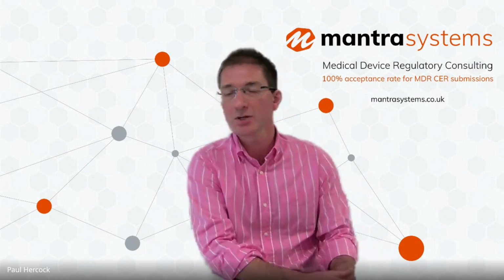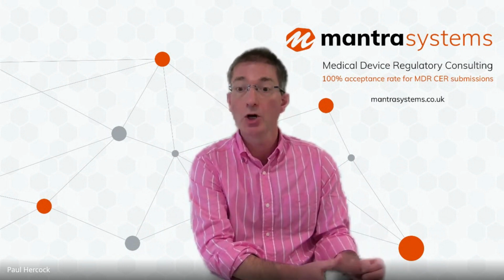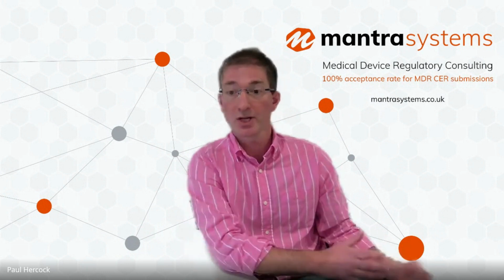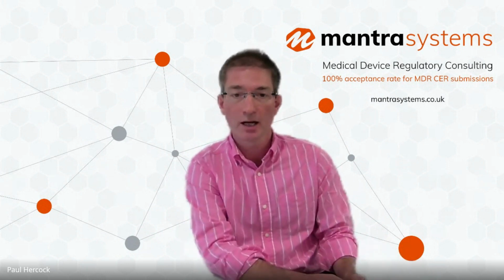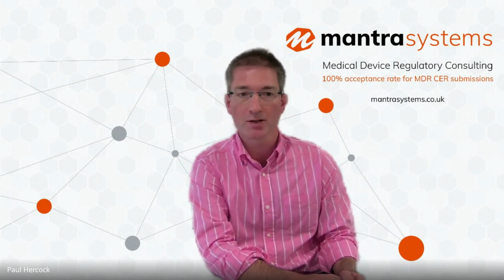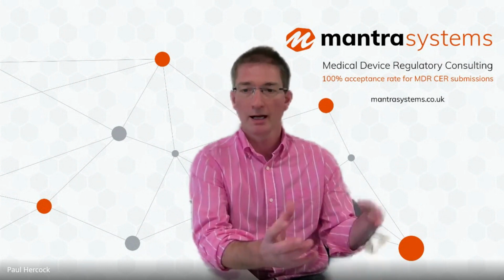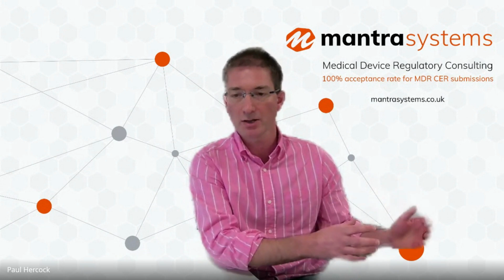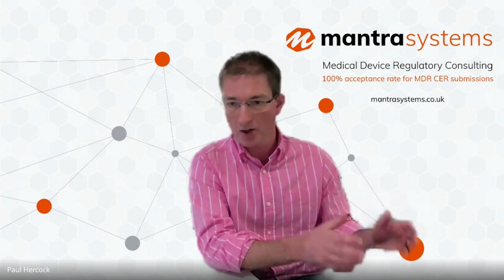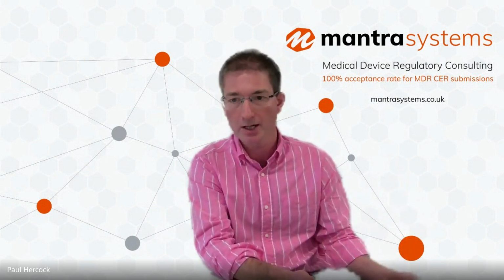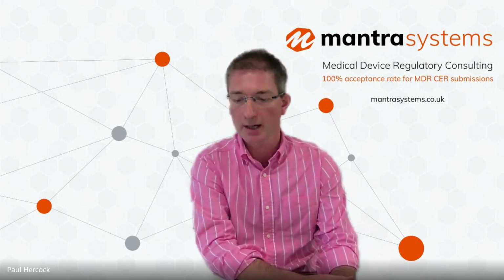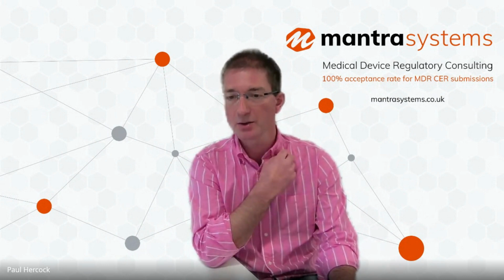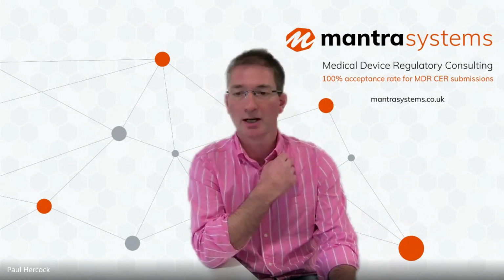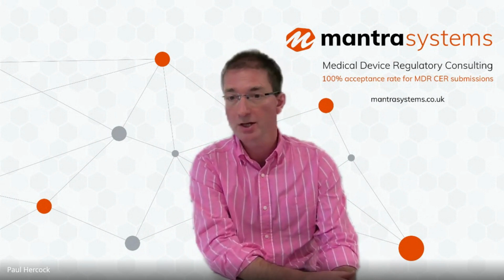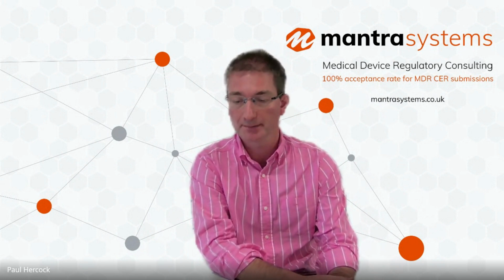Now, there might be some exclusions to that because it's not just performance data, but also safety data that we need to be considering. And it might be that there's some useful safety data related to an equivalent device. But I think you're blurring lines. I think if it's Article 61.10, then it should be a non-clinical route to conformity because you're saying it's inappropriate to use clinical data. So it wouldn't normally be relevant to 61.10. Just as an aside, using Article 61.10, though, does not remove the obligation to collect PMCF data on the product.